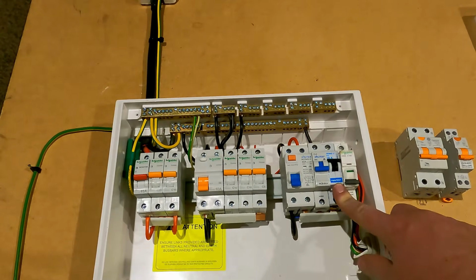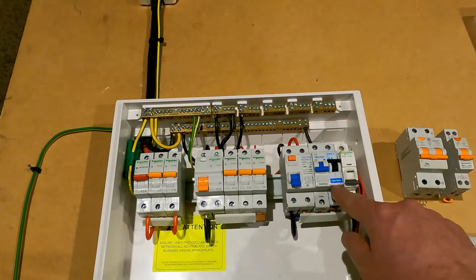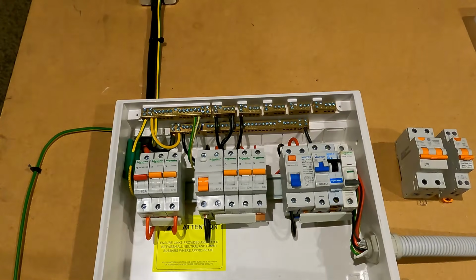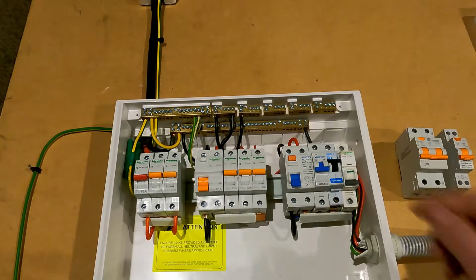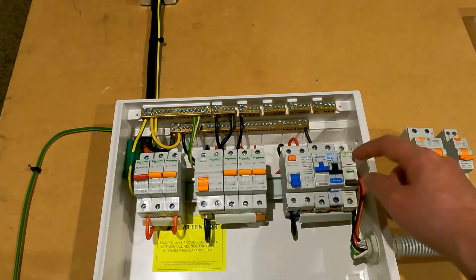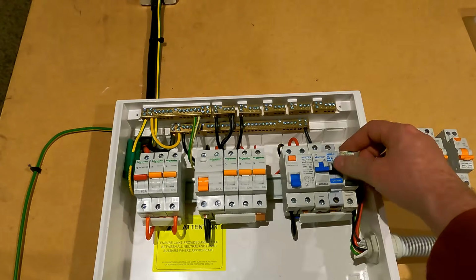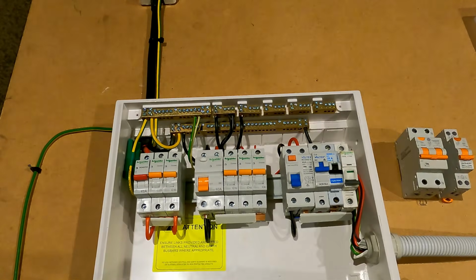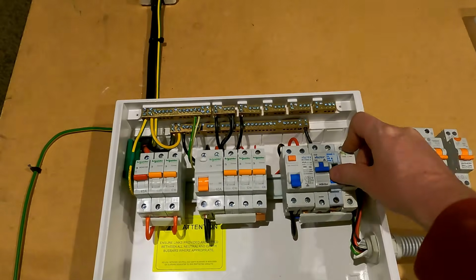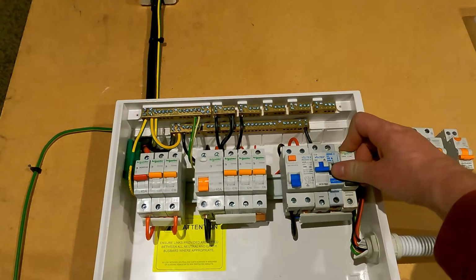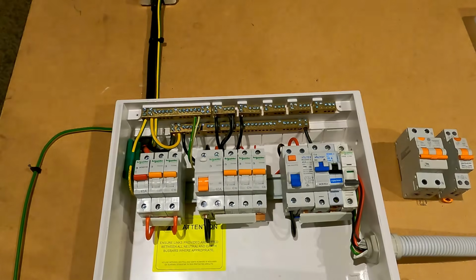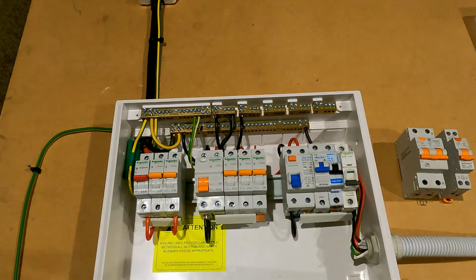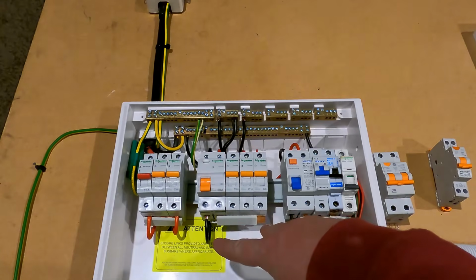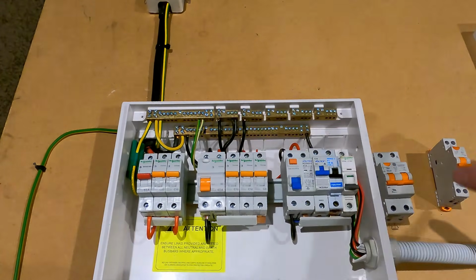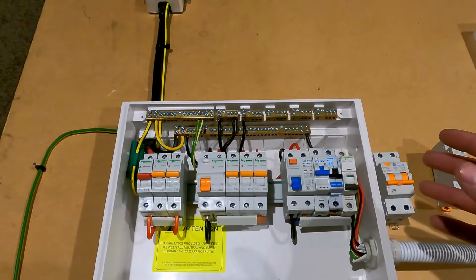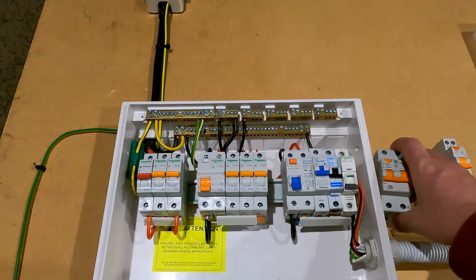This Vinkier circuit breaker, these ones here, if you see them in the field and you don't have to touch them, don't touch them. As soon as you activate them, you can struggle to turn them back on, just like so. So we tend to get rid of them. If you get lucky and somehow manage to turn it on and then it decides to spring down, you will get a callback and you'll have to go back there and replace it anyway. So along with fixing these two faults that I've seen, I'm going to get rid of this whole bunch entirely. It's no longer needed for this video, and I'll throw this RCBO in its place.